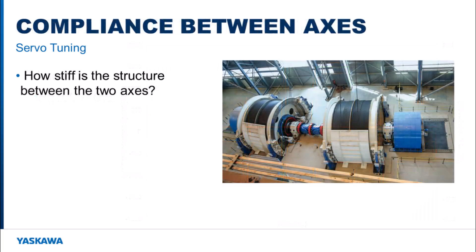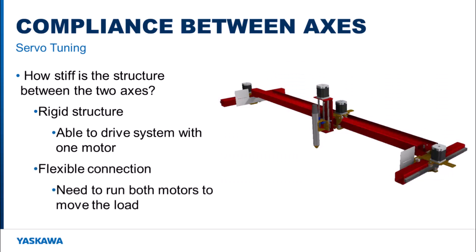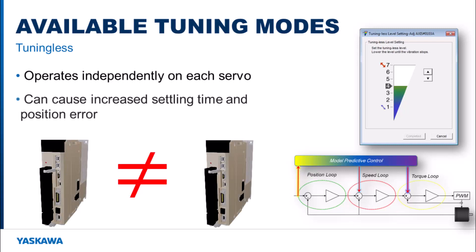Compliance between the master and slave axis plays a major part when trying to tune the dual-axis system. If the structure is rigid and the master motor can handle the full load, the slave axis could be disconnected and the motors can be tuned separately. If the connection between the motors is not rigid or flexes, then both motors need to be tuned at the same time so the machine does not bind up during tuning. Tuningless can be used but is not recommended because the tuningless algorithm is not shared between the amplifiers — the dynamic values may differ, causing increased settling time and in some cases increased position error.